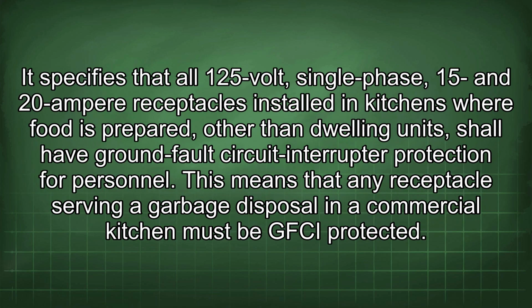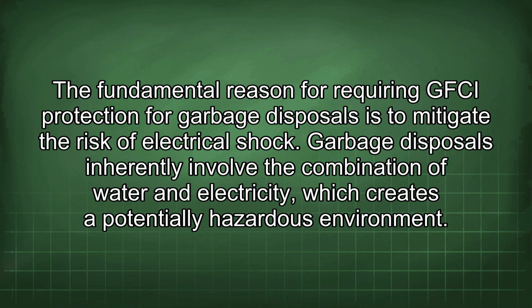It specifies that all 125-volt single-phase 15 and 20 ampere receptacles installed in kitchens where food is prepared, other than dwelling units, shall have ground fault circuit interrupter protection for personnel. This means that any receptacle serving a garbage disposal in a commercial kitchen must be GFCI protected. The fundamental reason for requiring GFCI protection for garbage disposals is to mitigate the risk of electrical shock. Garbage disposals inherently involve the combination of water and electricity, which creates a potentially hazardous environment.